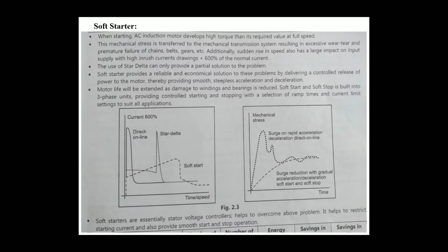The waveform below shows the comparison between the star delta starter, soft starter and direct online starter. As shown in the first waveform, at the time of starting, the peak point of the direct online starter is very high. Then for the star delta starter the peak point is low, because at the time of starting the motor operates on star, but when the motor speed comes to 80% of normal speed, the motor changes the starter from star to delta position. At that time the motor current is maximum.